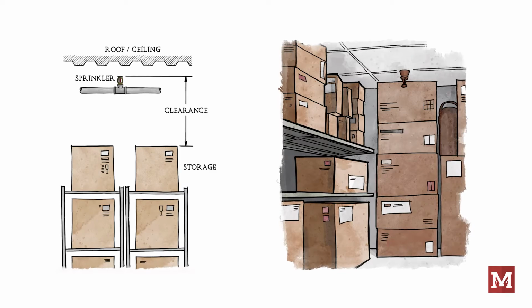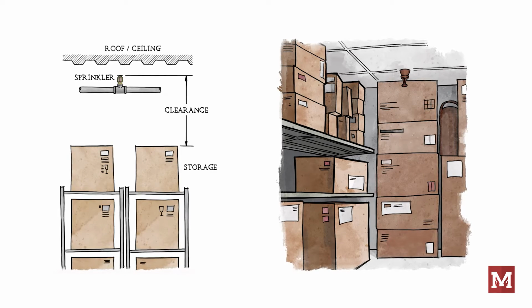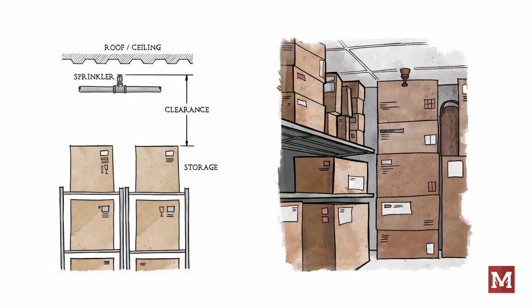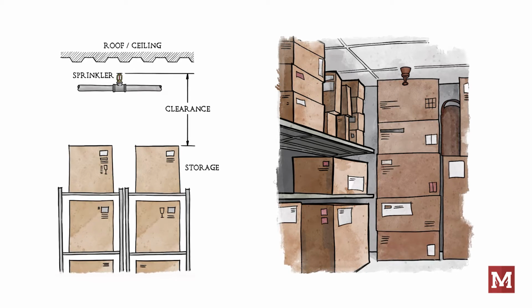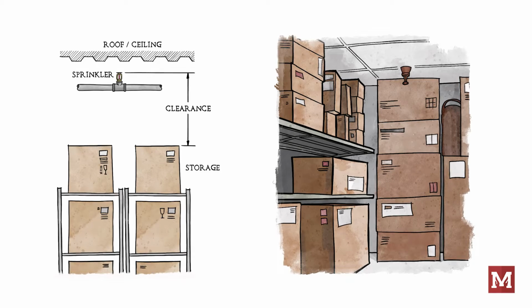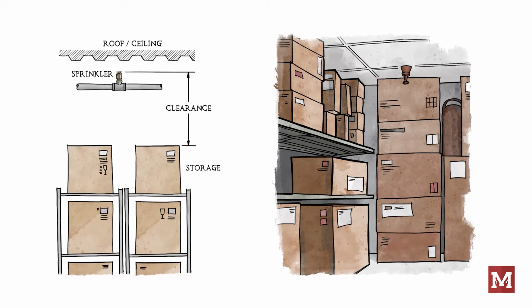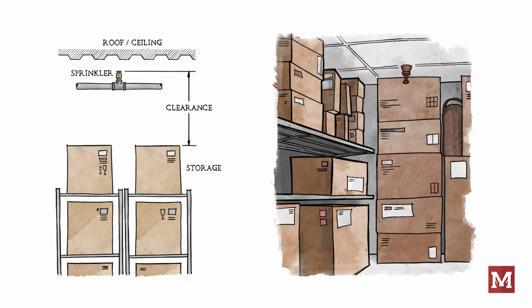One important note is that this doesn't apply when the storage is against a wall. You won't properly protect the goods that are stored too high, but this does not present an obstruction to the water discharge. Here, it's important to check against the allowed height of the storage for the area. Discharge isn't a concern though.